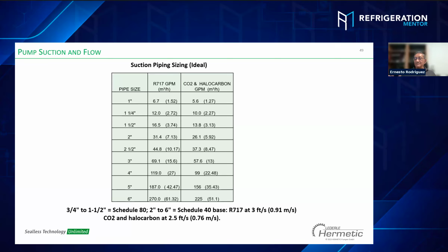In open type pumps, it's going to keep running, but the problem with open type pumps is you need to replace the seals constantly, in a very short time, maybe 3 months, maybe 6 months. And is that failure due to overheating of the pump? Usually, I think it is turbulence, a mix. Turbulence, flashing gas, a lot of things happen when you choke the pump by undersizing the suction. Okay, perfect.